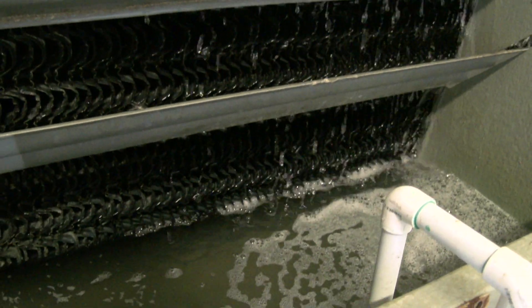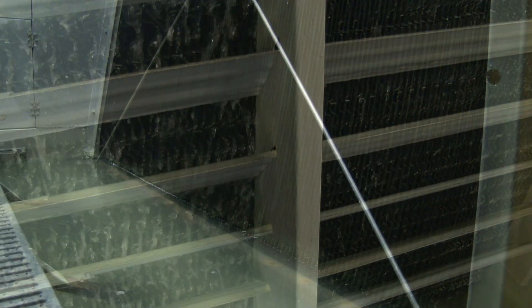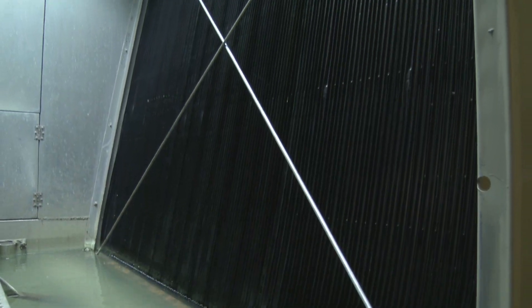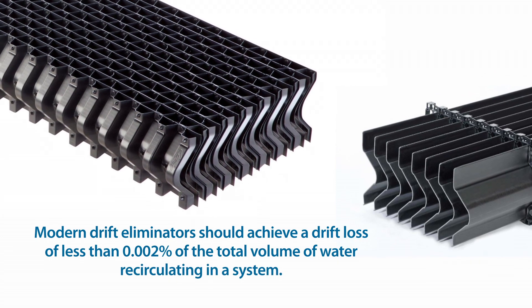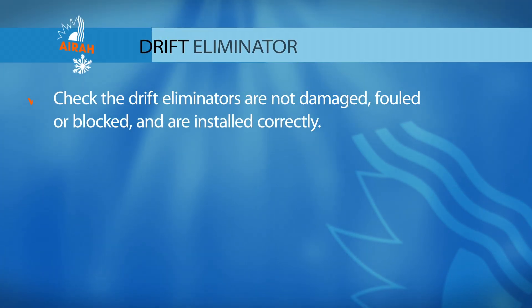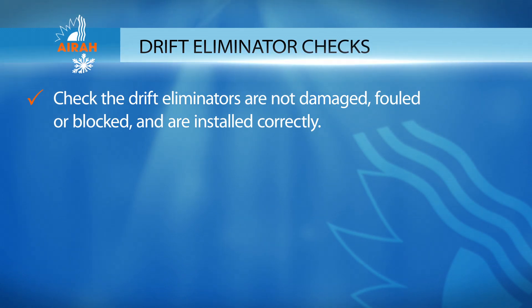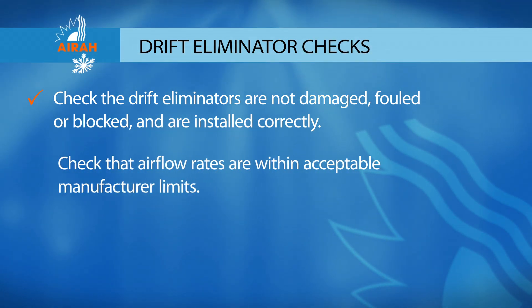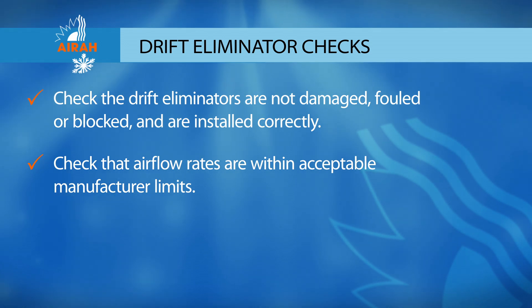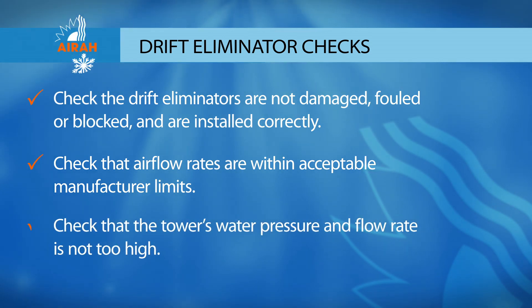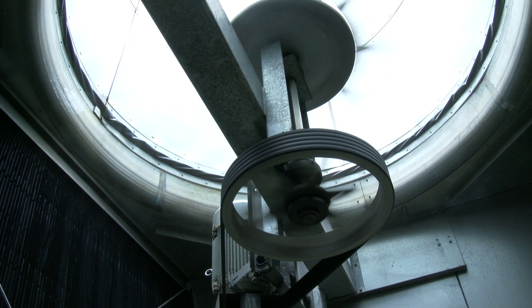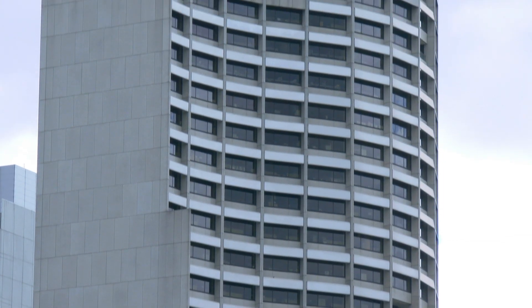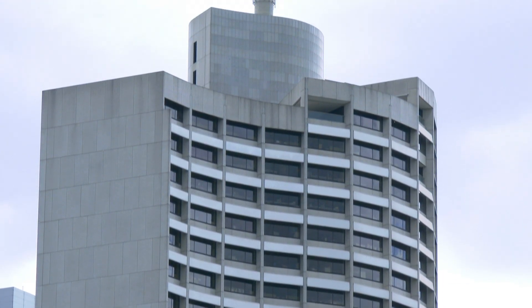Drift is largely controlled by the tower's design and operation, and in particular by the design of the drift eliminator. Modern drift eliminators should achieve a drift loss of less than 0.002% of the total volume of water recirculating in a system. Check the drift eliminators are not damaged, fouled, or blocked, and are installed correctly. Check that the airflow rates are within acceptable manufacturer limits, and that the tower's water pressure and flow rate is not too high. Controlling fan speeds and the prevention of ambient wind on the tower are ways of reducing potential drift losses further.